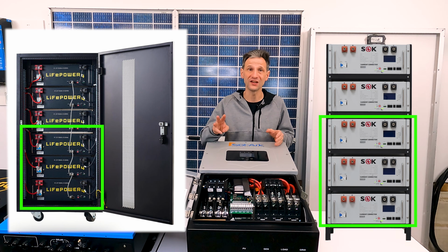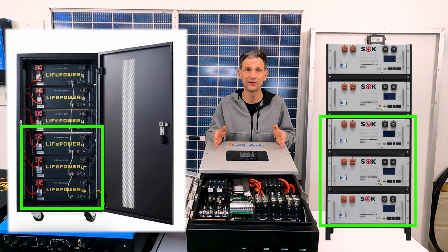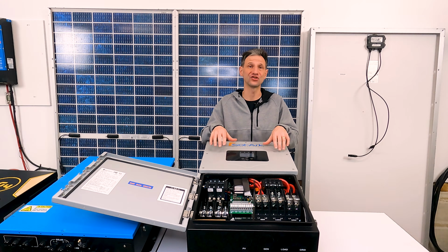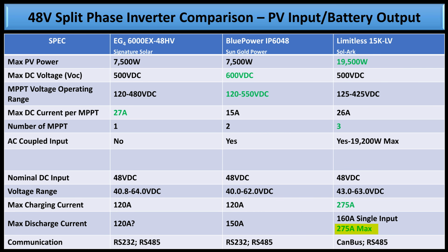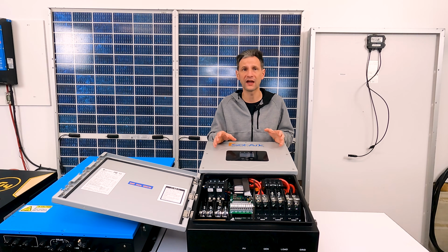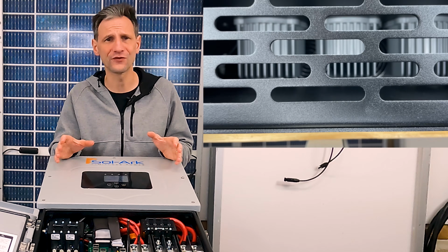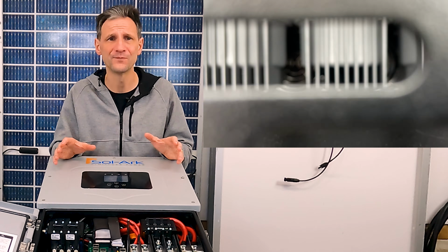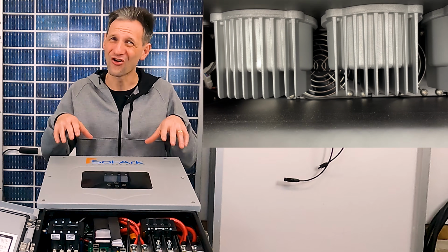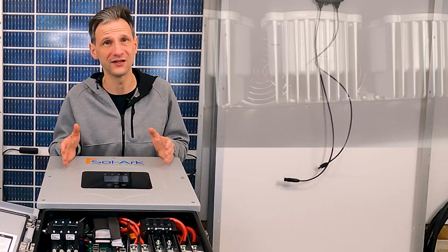starting with at least 3 48-volt server rack batteries. This unit can provide a significant 275 amps of charge and discharge current if you use both battery input connections. It has an RS-485 port for connecting to the battery BMS for automatic management and tracking of battery capacity. This unit has a lot of other features that I haven't mentioned here today. If you have the budget, it's hard to go wrong with the Sol-Ark 15K.